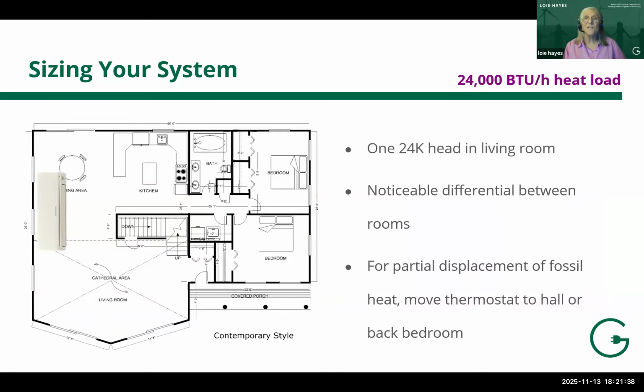Now, I want to make sure you understand the importance of sizing the equipment, and in particular, avoiding oversizing. So in this instance, we're estimating a building that has a heat load of 24,000 BTUs, that's British thermal units. And in this particular illustration, I'll show you two examples of this same floor plan. We're positing a 24,000 BTU head in the main open area.